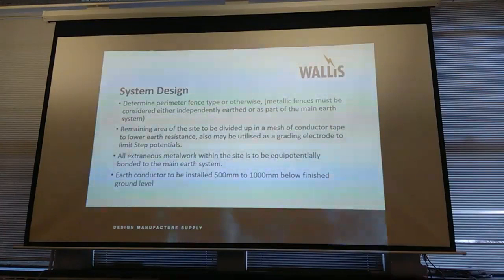Earth conductors should be installed between 500 and 1,000 mil below finished ground level. The idea behind that is, below about 300-ish mil, even with the worst winter in the UK, the ground should not freeze. If the ground freezes, the resistivity actually goes through the roof. The resistivity changes in frozen ground.